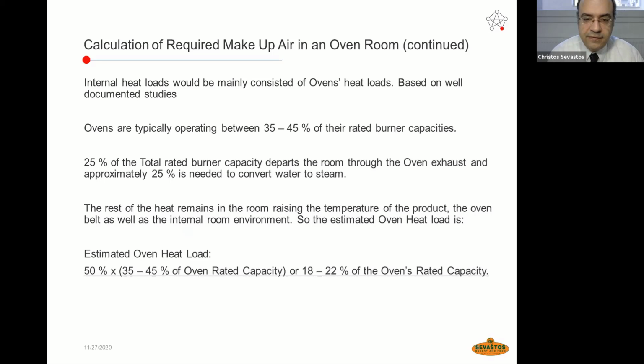How is this calculation made, and on which factors is it based? Internal heat loads will be mainly consisting of oven heat loads. The ovens are typically operating between 35 to 45% of their rated burner capacity. 25% of the total rated burner capacity departs the room through the oven exhaust. 25% of the rated heat is needed in order to convert water to steam, in order to make the baking of the product. And the rest of the heat is remaining in the room, raising the temperature of the product, the oven belt, as well as the internal room environment.